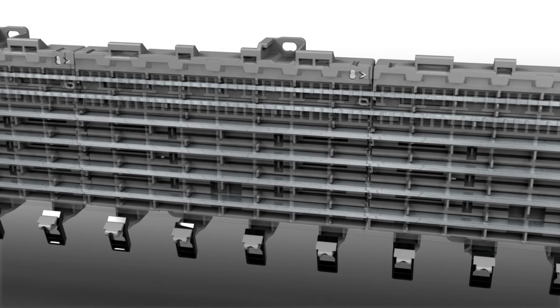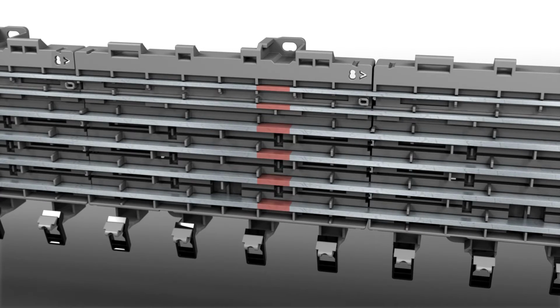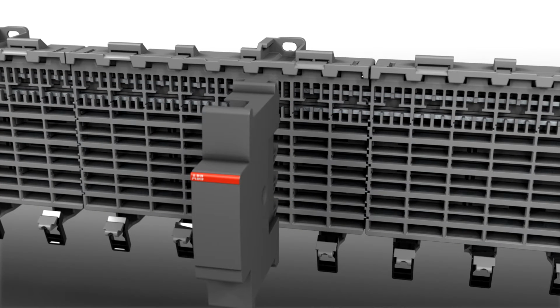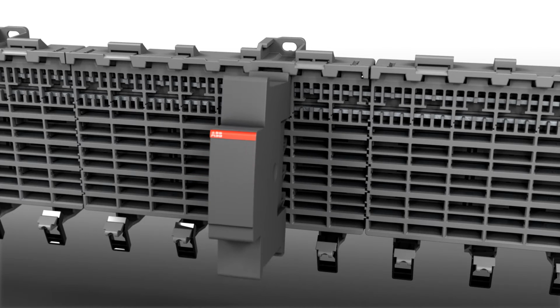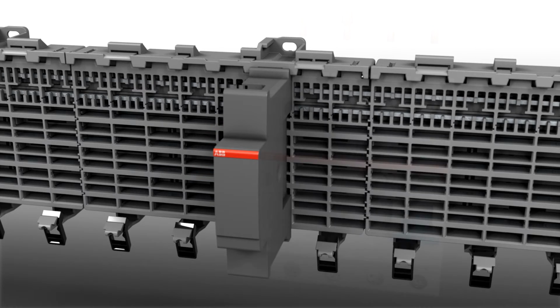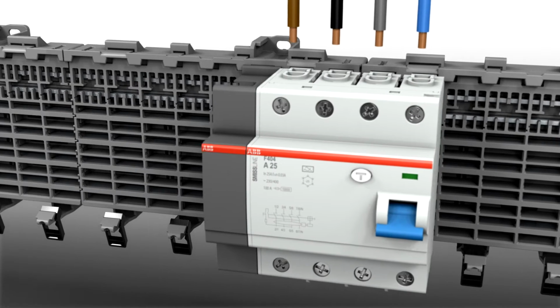Bus bars can be isolated. Using an isolator, this allows you to create different circuits on the sockets. By doing this, you can create groups that are protected against residual currents, for example. In such cases, power is supplied via a residual current circuit breaker.